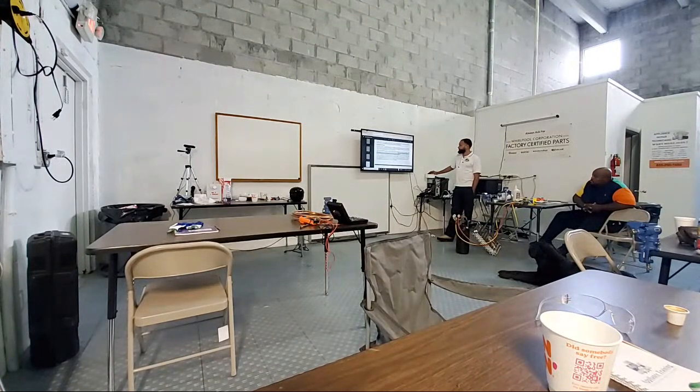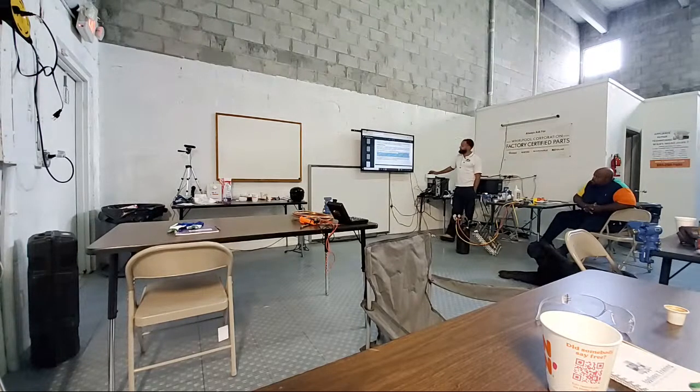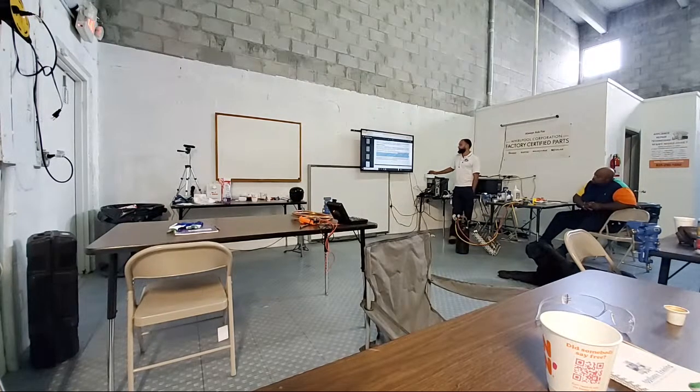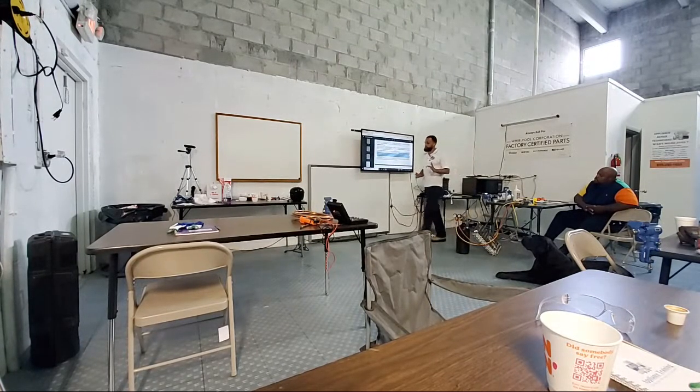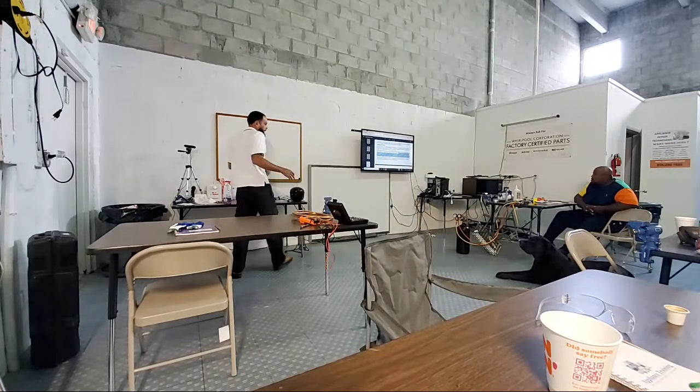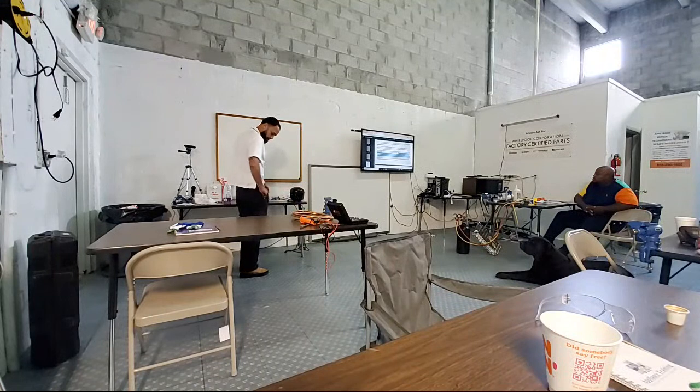The heater, one more time. The heater will heat the evaporator and melt the frost. The thermostat monitors the evaporator temperature, and when heat is sufficient, the heater de-energizes. Okay, it turns off. This thermostat is often called a defrost termination thermostat or defrost terminator. The target temperature is usually between 40 and 60 degrees. At that point, the thermostat opens. We haven't gotten into electrical yet, but I'll show you a quick drawing.